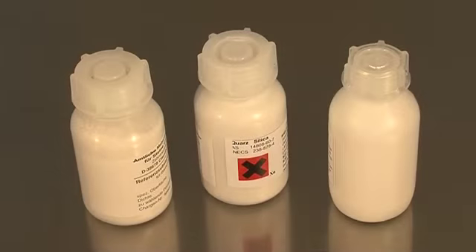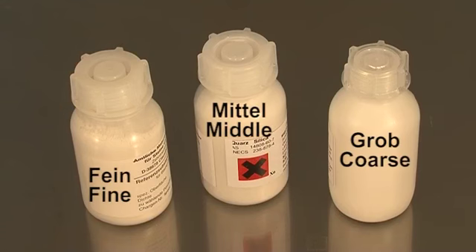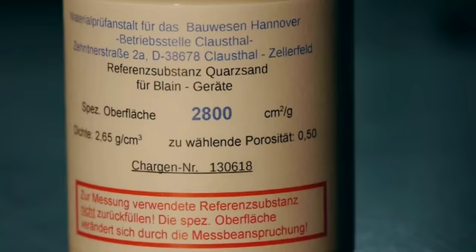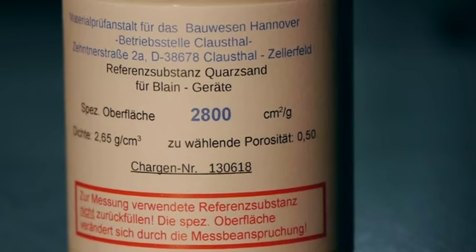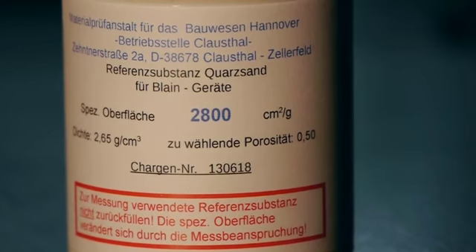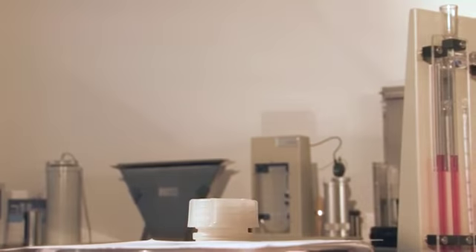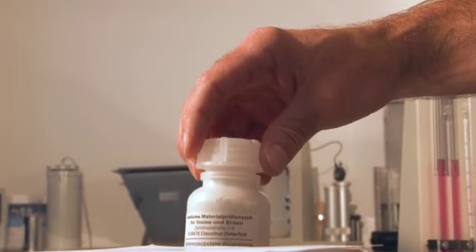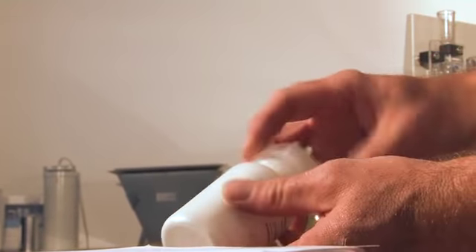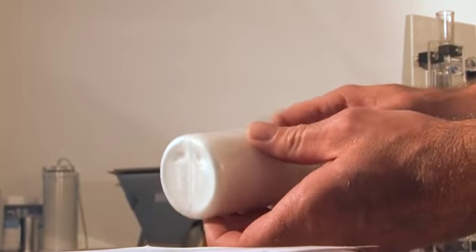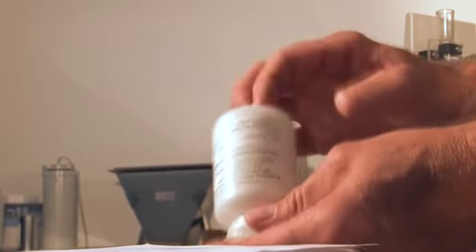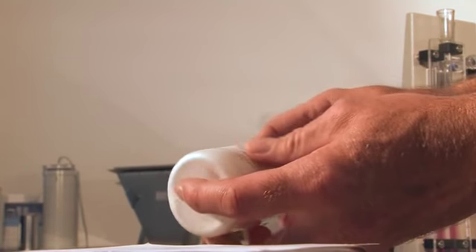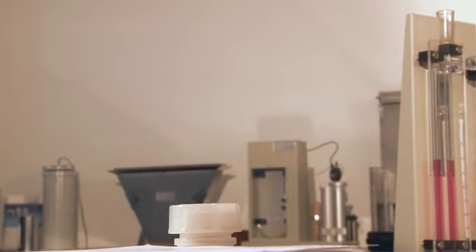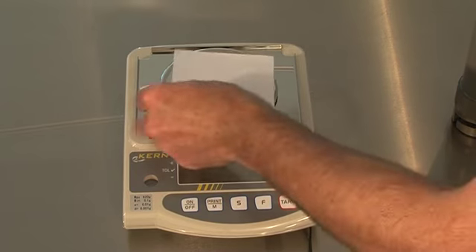The apparatus calibration is now carried out on the basis of these selected test substances. The corresponding apparatus constant is now determined for this reference substance. The selected test substance is shaken for at least 2 minutes in a bottle with a screw lid to dissolve any agglomerates. The bottle is then left to stand for 2 minutes. Subsequently, the powder bed is stirred with a clean, dry rod in order to evenly distribute the fine particles.